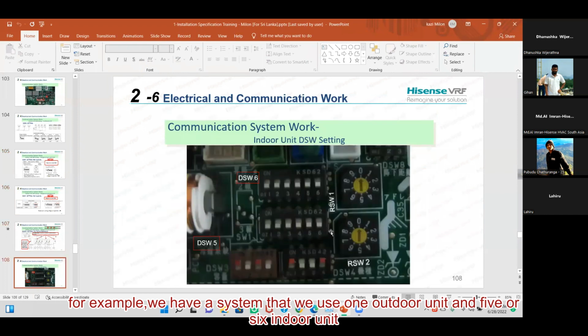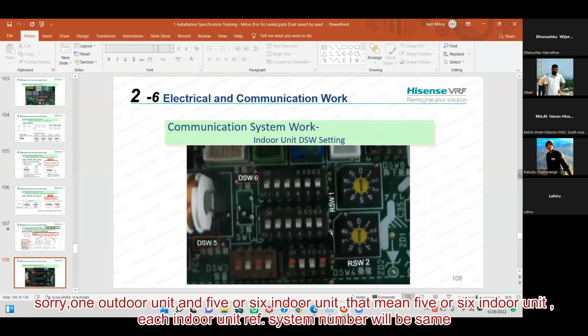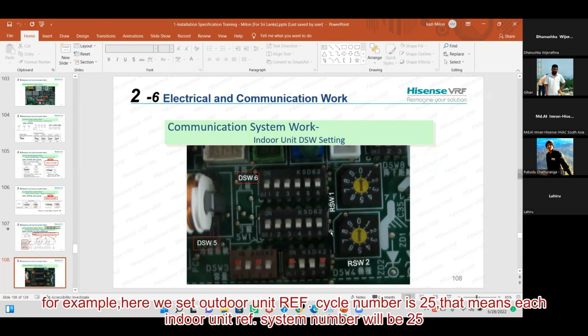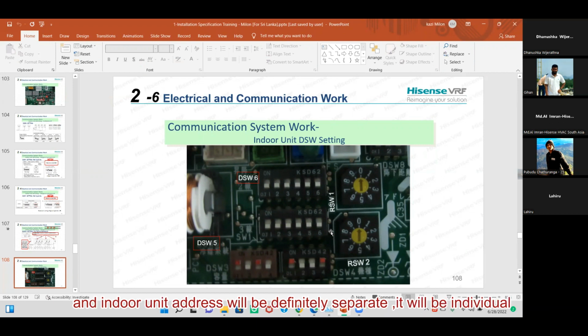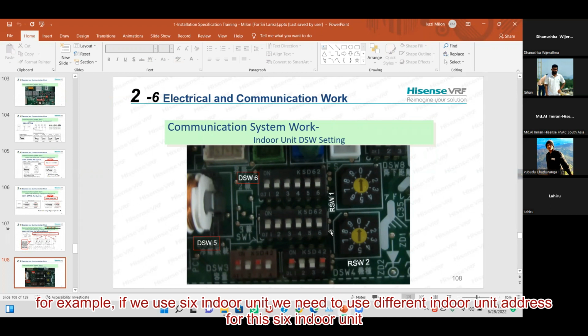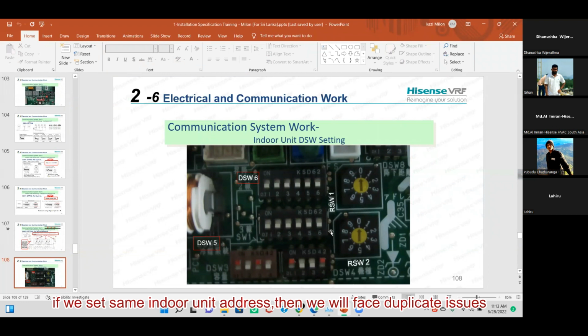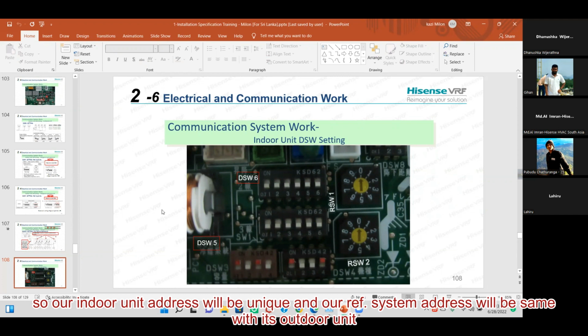For example, we have a system where we use one outdoor unit and 5 or 6 indoor units. That means each of the 5 or 6 indoor units' refrigerant system number will be the same. For example, if we set the outdoor unit refrigerant cycle number to 25, each indoor unit refrigerant system number will be 25. And the indoor unit address will definitely be separate. It will be individual. For example, if we use 6 indoor units, we need a unique indoor unit address for each of these 6 indoor units. If we set the same indoor unit address, then we will face a duplicate address error. So our indoor unit address will be unique, and our refrigerant system address will be the same as its outdoor unit.